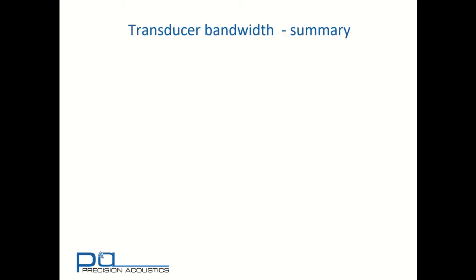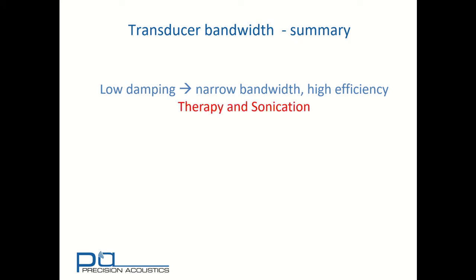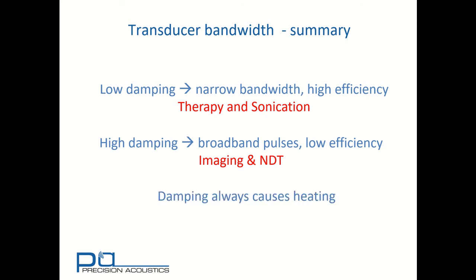So to summarize, we've seen that low damping transducers have a narrow bandwidth but very high efficiency. This is typical of therapy and sonication applications. High damping transducers lead to very short broadband pulses, but the efficiency has been reduced, and we typically find these in imaging and non-destructive testing applications. And damping always causes heating.